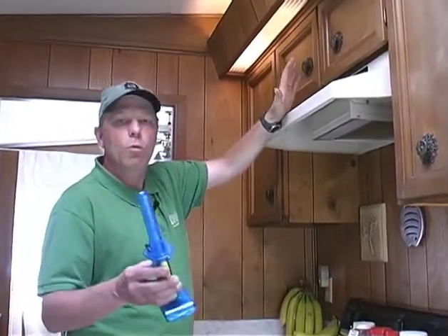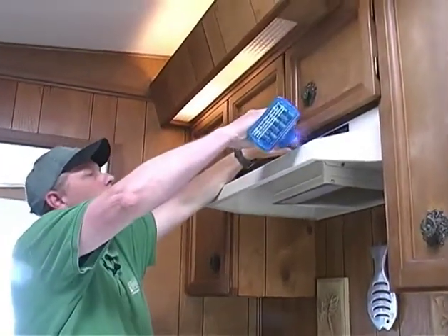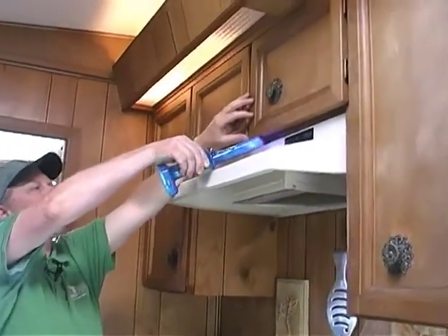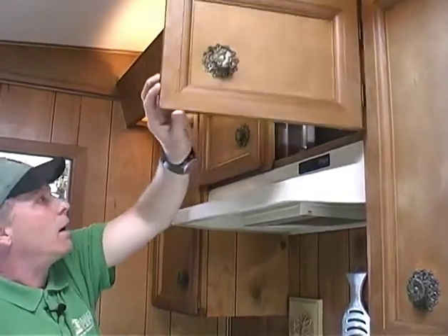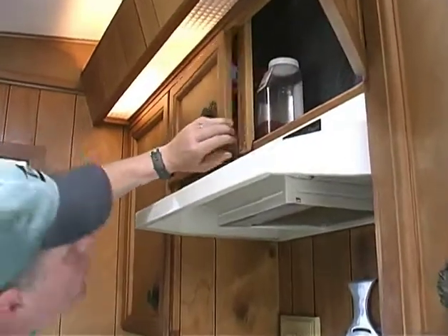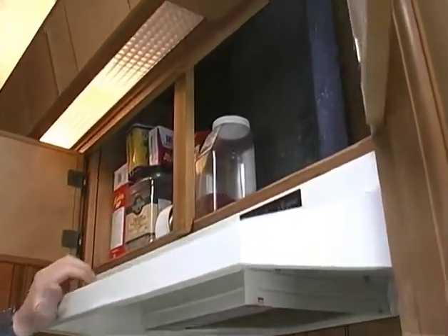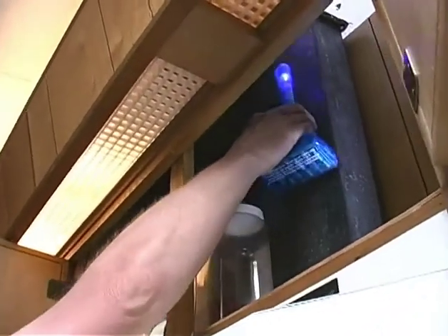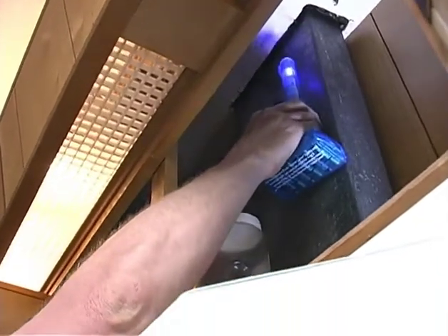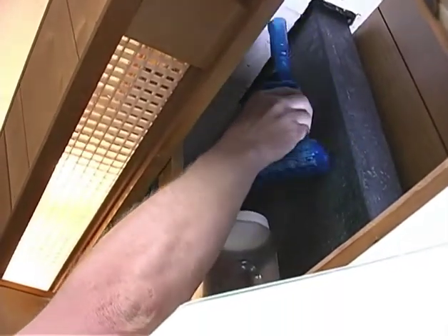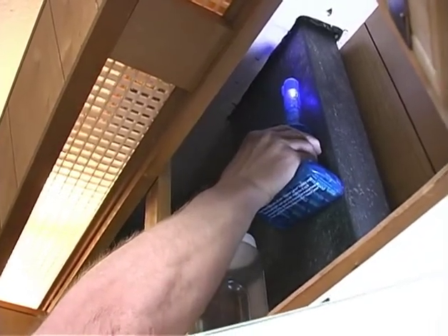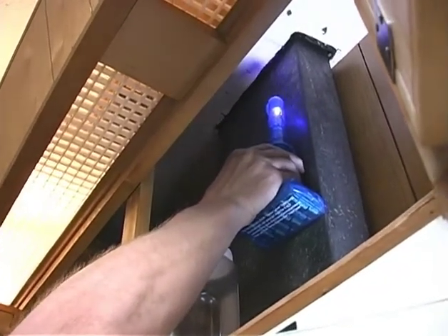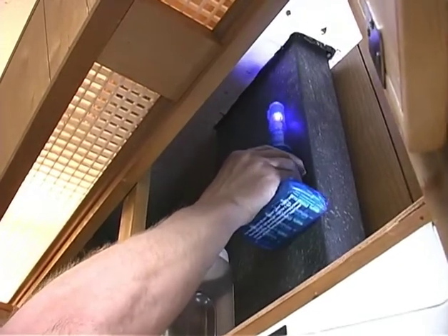So I have my smoke pencil. I can feel air moving through here, and we can see air moving out of this cabinet. I'll open the cabinet, and there's definitely a hole up there. Let's see what this looks like with the smoke pencil. You can see the air is just coming out of the bottom of the smoke pencil because it's just a lot of air moving through here. And today it's hot air, and you can smell the attic.